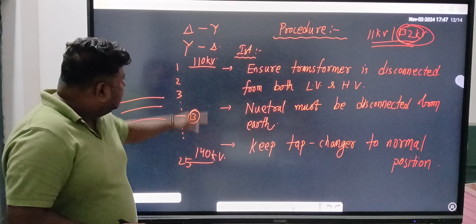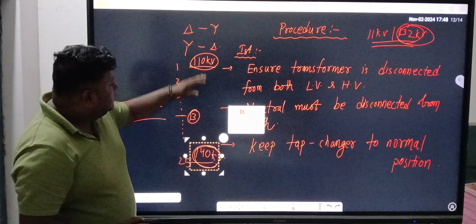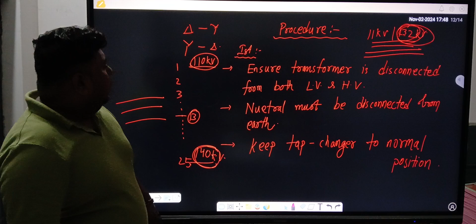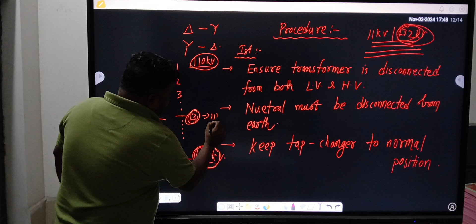So under this condition, what is the meaning of this tapping? This means under 110 kilovolt or under 140. This is the minimum range, this is the maximum range. So under this range also it can work with this value, means it is self-sufficient or it is safe to provide this 132 kV under this minimum and maximum condition. This is the meaning of tapping. In summarizing way, I have just told what is the meaning of tapping. Okay. So now normal position means what? Suppose 13 is rated as 11 by 132. Tap number 13.